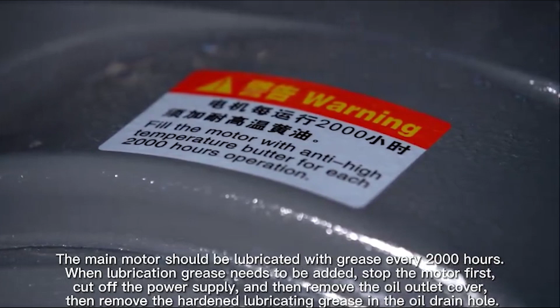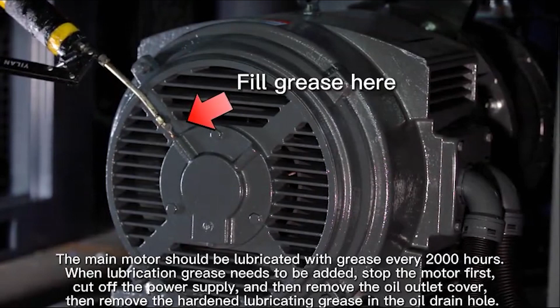The main motor should be lubricated with grease every 2000 hours. When lubrication grease needs to be added, stop the motor first, cut off the power supply, and then remove the oil outlet cover. Then remove the old lubricating grease in the oil drain hole.